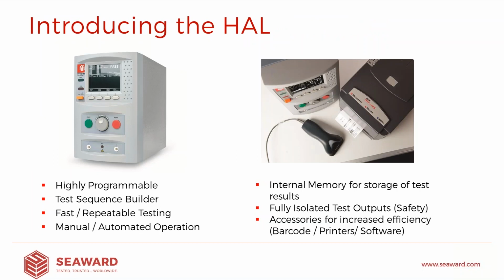Thanks again for staying on for the presentation. We'd like to briefly introduce you to our industry-leading range of production line safety testers, the HAL series. Designed to increase productivity during tests, the HAL is a highly flexible tool for electrical manufacturers. Each HAL is capable of storing up to 6,000 test records and has the ability to download the results to a PC. Combined with a barcode scanner, full traceability of your product testing can be kept, giving you peace of mind. The HAL series is fully programmable. Test sequences can be created and stored, ensuring that the products are tested correctly time after time. For those wanting an automated system, the HAL can be fully remote controlled and integrated into any system.